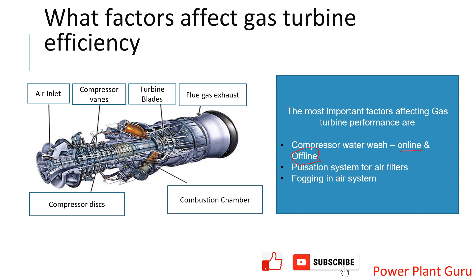Third is the fogging system for inlet air. Ambient air temperature greatly impacts machine performance and output, but you cannot control it directly. At some installations, a fogging system sprays a mist of fine water particles at the gas turbine inlet to reduce the air temperature. If you have that system in your plant, you can use it. So effectively, the three handles to optimize gas turbine efficiency and heat rate are: regular compressor water wash using online and offline methods, effective operation of the pulsation system to keep inlet air filters clean, and use of the fogging system to reduce inlet air temperature.